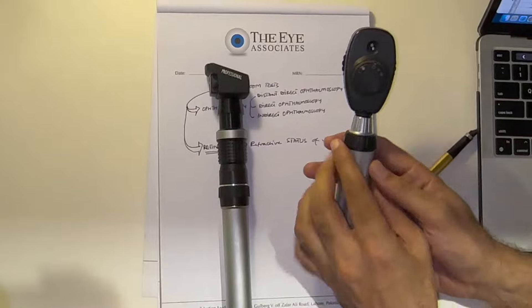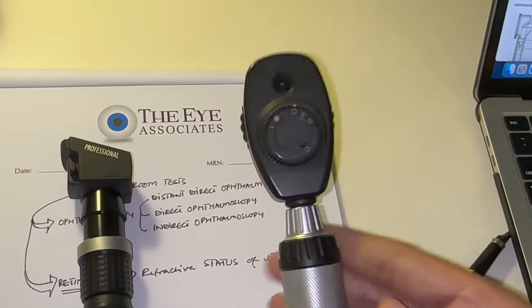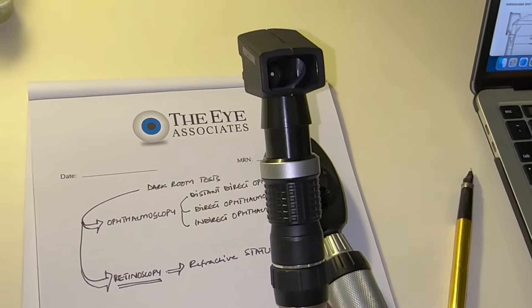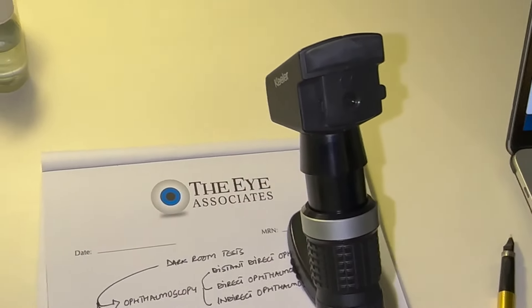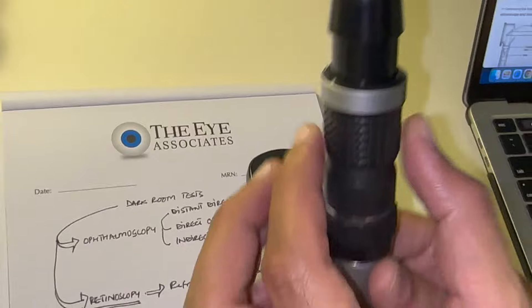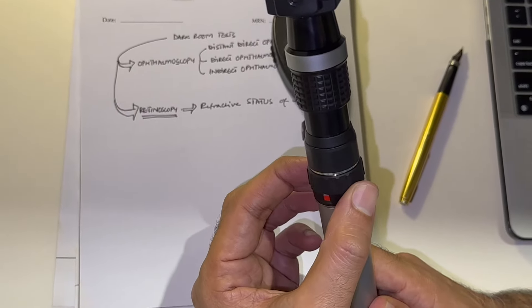The first step is to differentiate between an ophthalmoscope and a retinoscope. Unlike an ophthalmoscope which has an aperture with different settings, a retinoscope does not have an aperture — it just has an opening containing either a plane mirror or a concave mirror. It has an eyepiece through which the examiner looks at the glow coming in, and also a focusing sleeve.